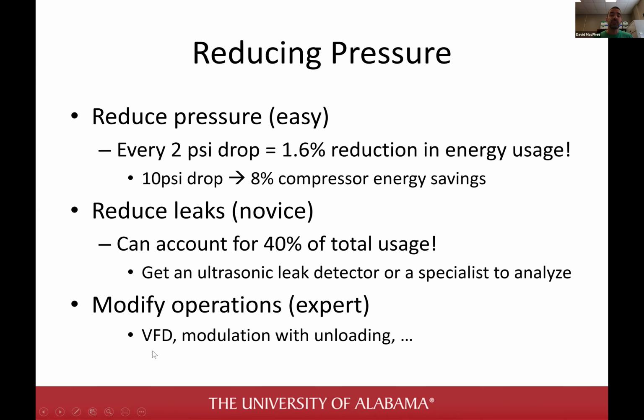But you can change the control strategy sometimes by going to your compressor. There may be a way for you to seriously change it from load unload to modulating with unloading, or vice versa. And so I've seen this many times. Or you can actually switch out a compressor for one with a VFD, or you can call some vendors and see if you can install a VFD on your air compressor if they're load unload.